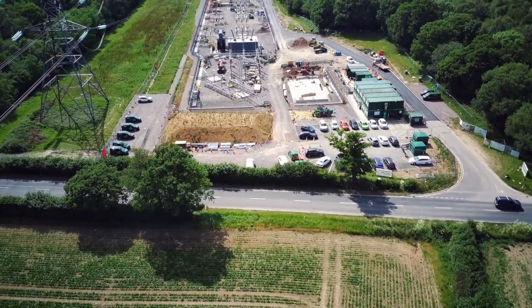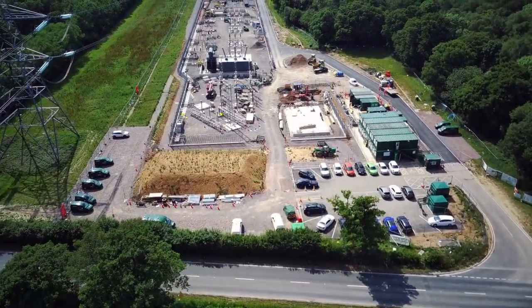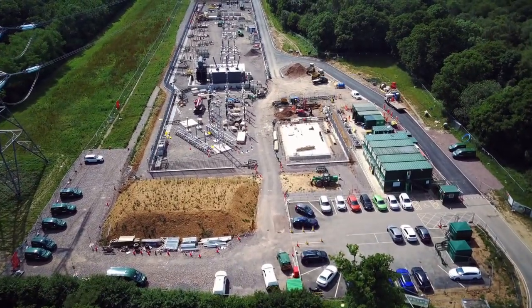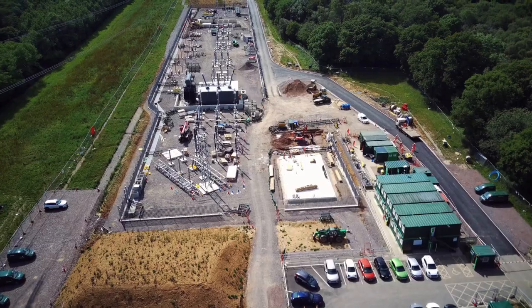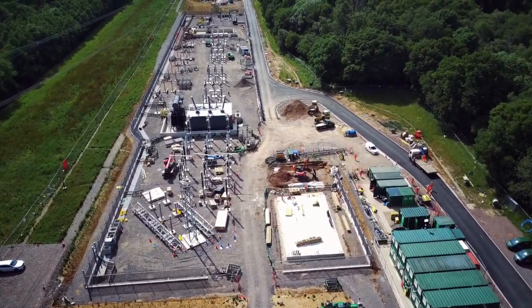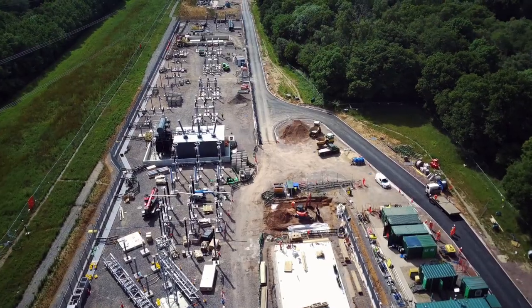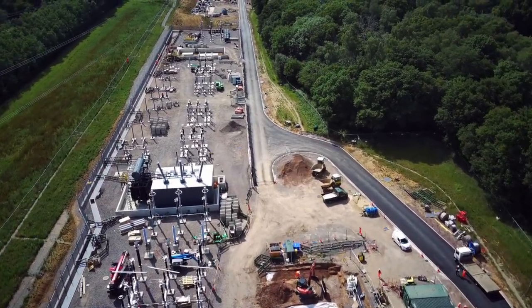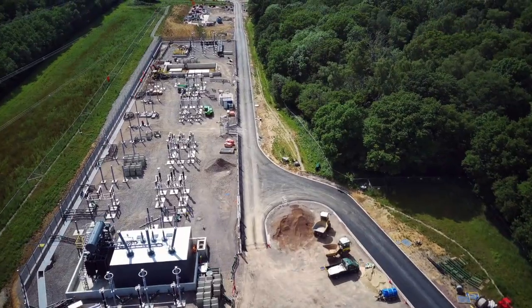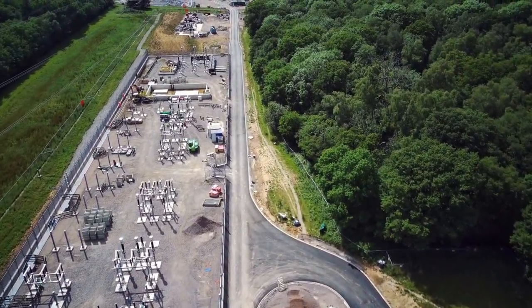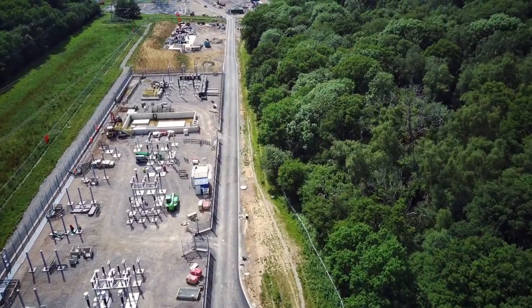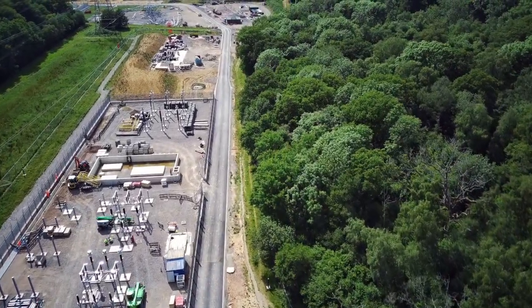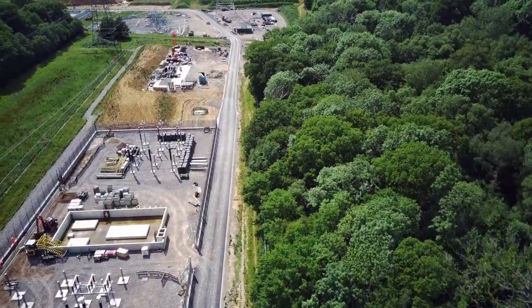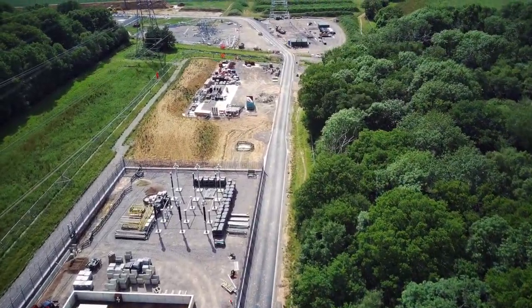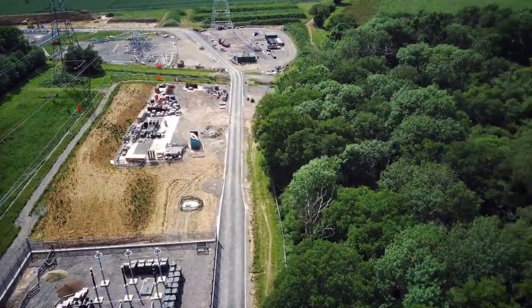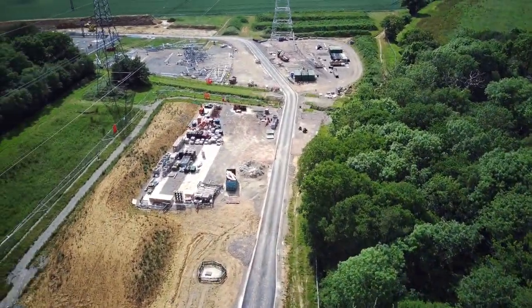What you're looking at is the entrance point to the substation with a supergrid pylon on our left, and coming into view the gantries that will take the wires coming down from that pylon to connect into the substation and to the supergrid transformer passing below us. There is further equipment on site I won't try explaining, but what we're now passing, the walled structure, is where the second supergrid transformer will be located when it's delivered later.